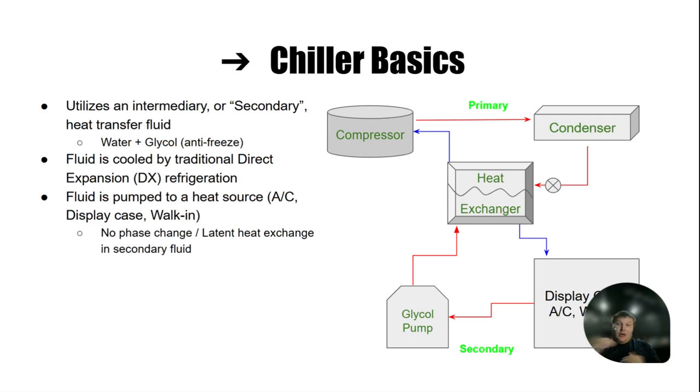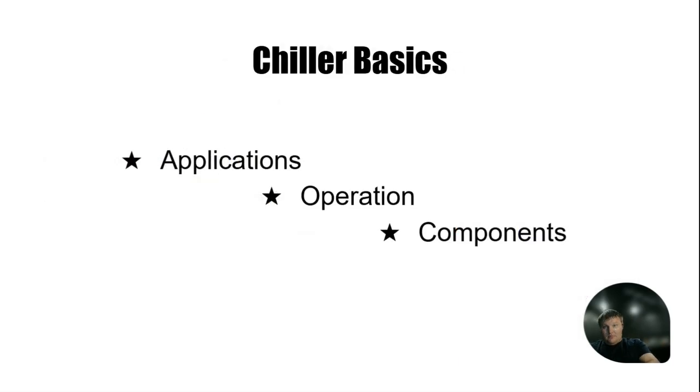Now, it's broken up into two separate sections. The primary side, that's the standard refrigeration cycle using traditional refrigerants. And then the secondary side, that's the glycol system. And then, again, an important call out is there is no phase change in the secondary fluid, in the glycol. We're going to go over some applications, operations, and components.